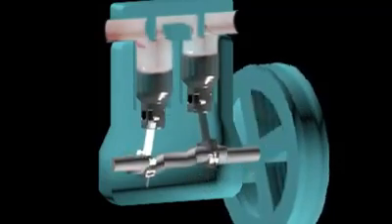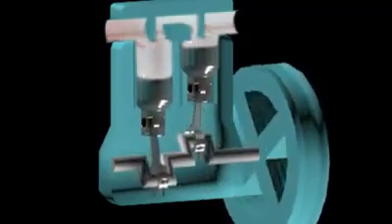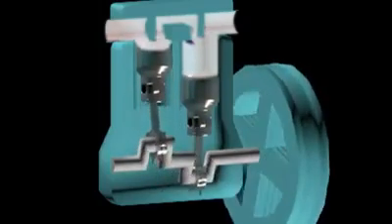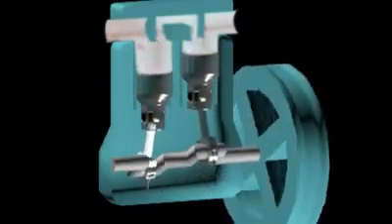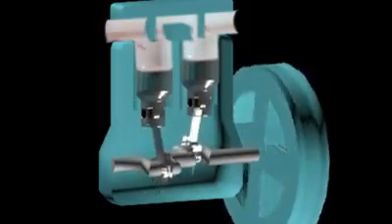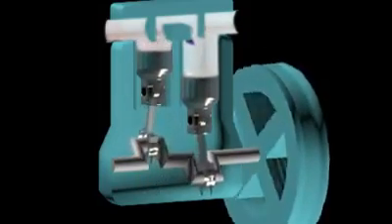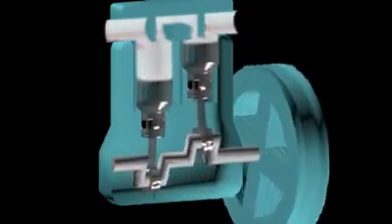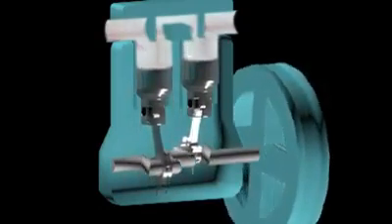On the suction stroke, where the piston is moving downward, the clearance space between the piston and the cylinder head will expand. The drop of the pressure will open the plate-type suction valve and force the refrigerant to enter the chamber until such time as the suction valve recedes.